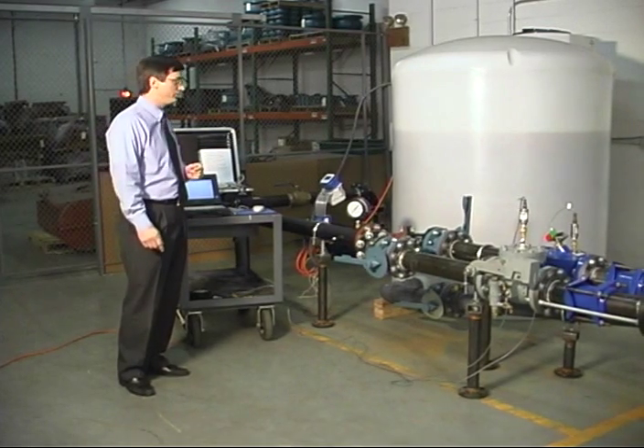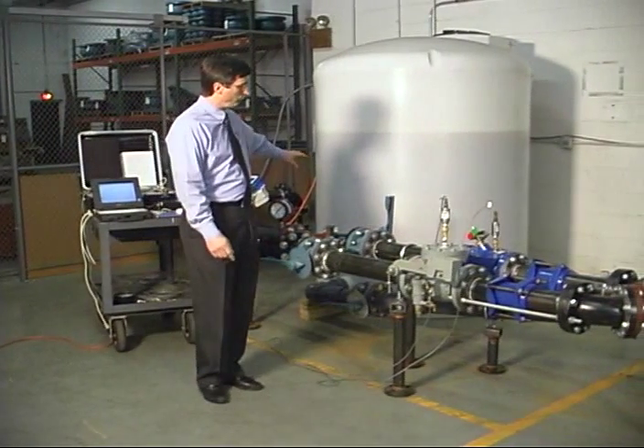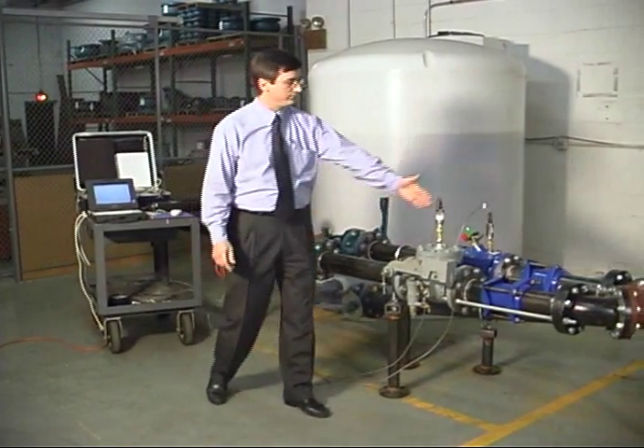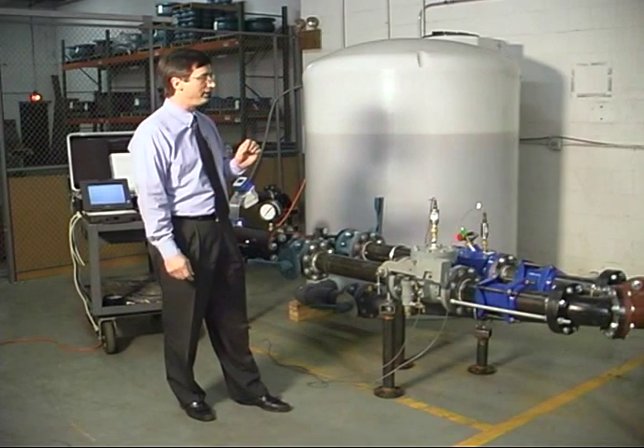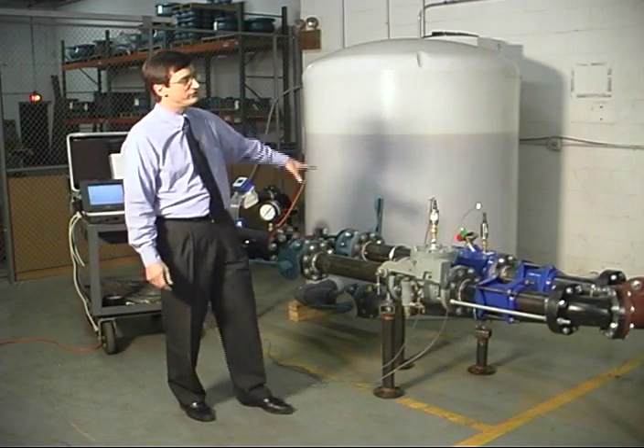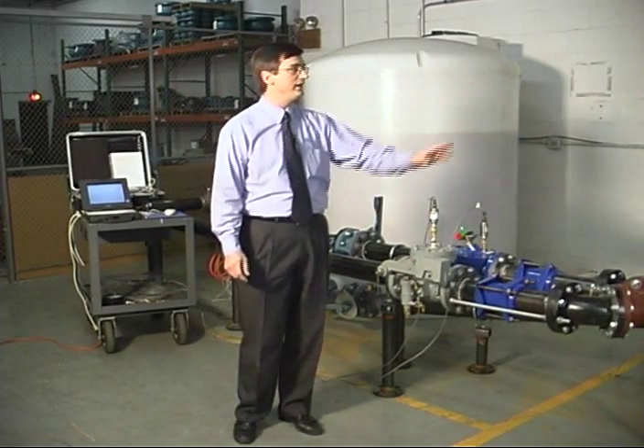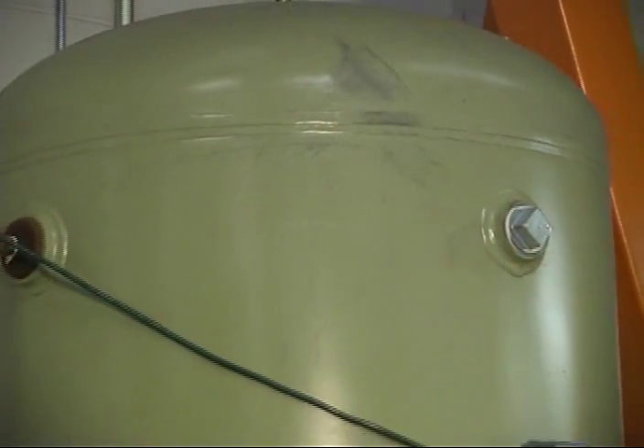With that, I'll get going to the testing. We're going to start the test with water flow through this side of the flow line, which is the cushion swing check valve. When I turn the pump on, we're going to send water for about 10 seconds through this valve. You'll see this valve open up, and water will flow into the air over water tank.